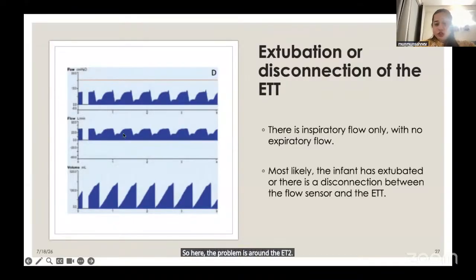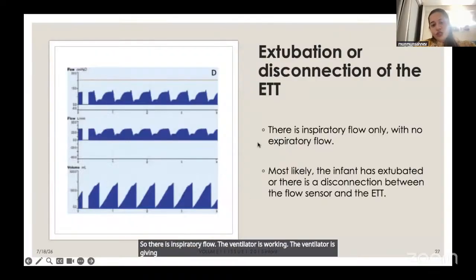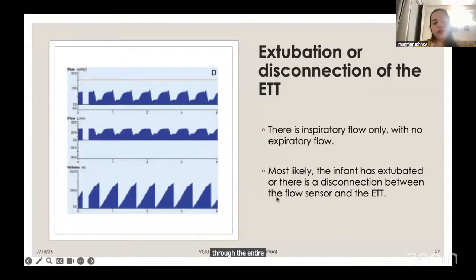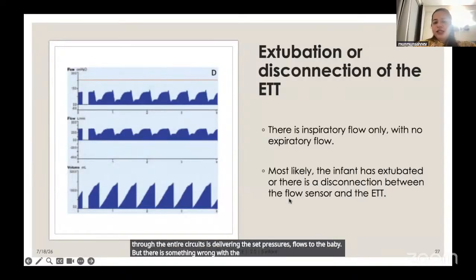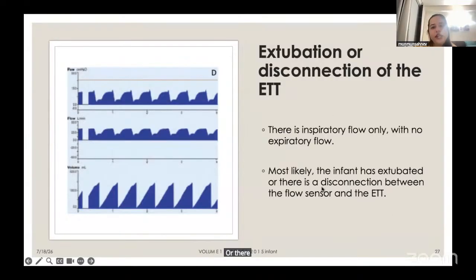So there is inspiratory flow. The ventilator is working. The ventilator is delivering the set pressures and flows through the entire circuit to the baby. But there is something wrong with the ET tube, that there is leakage of air around the ET tube and no expiratory flow is delivered. So most likely the infant has extubated, or there is a disconnection in or near the ET tube.